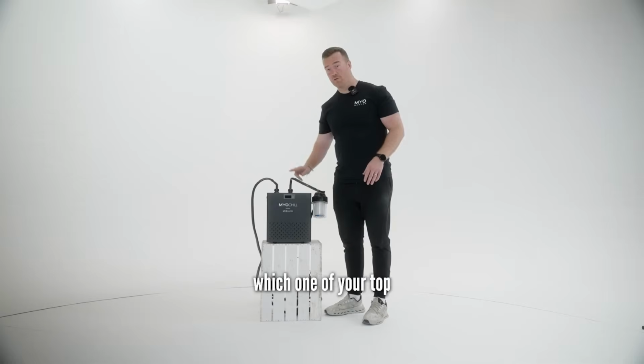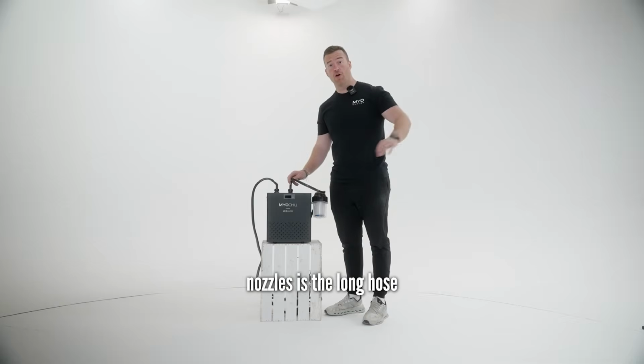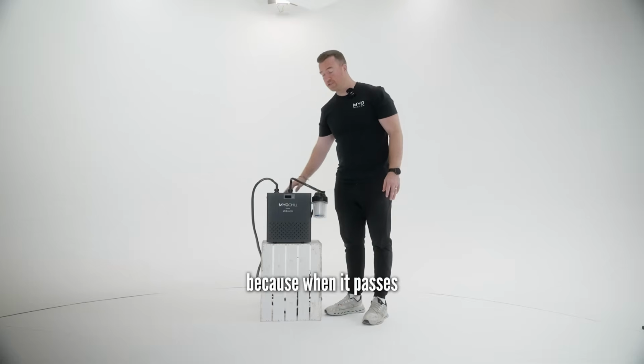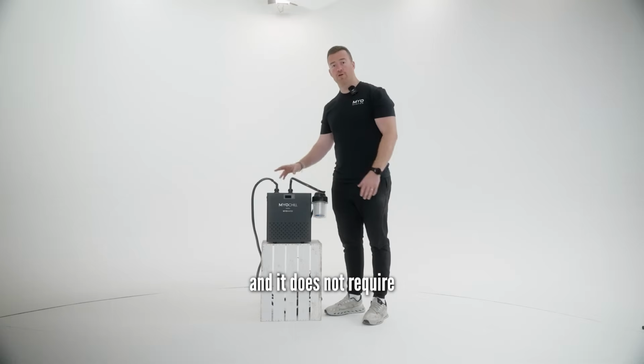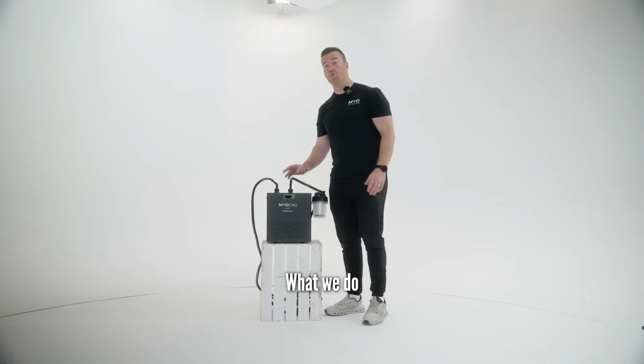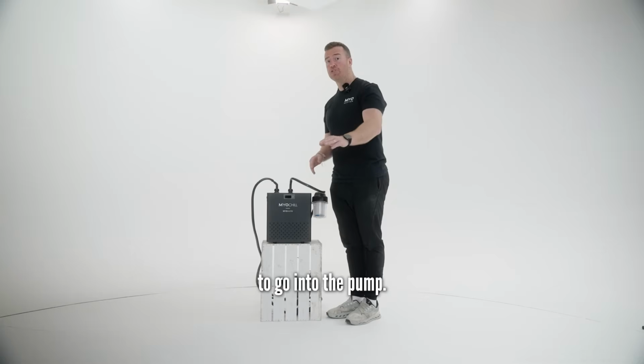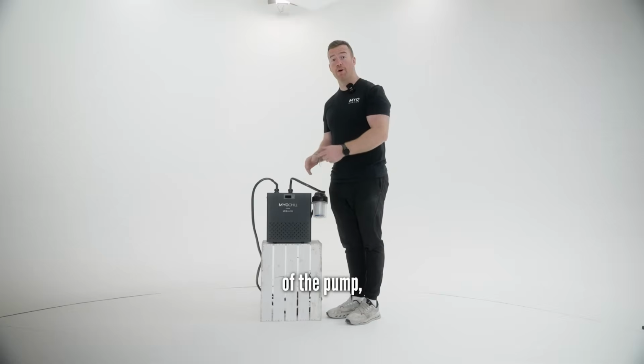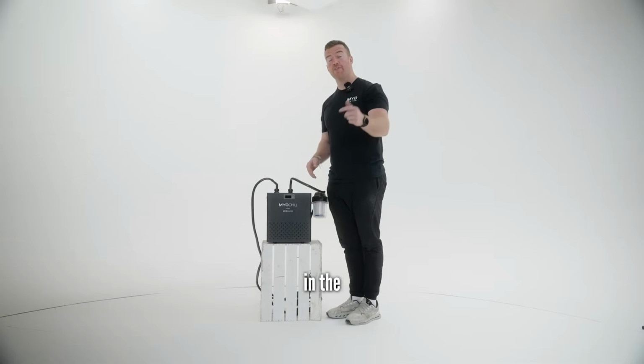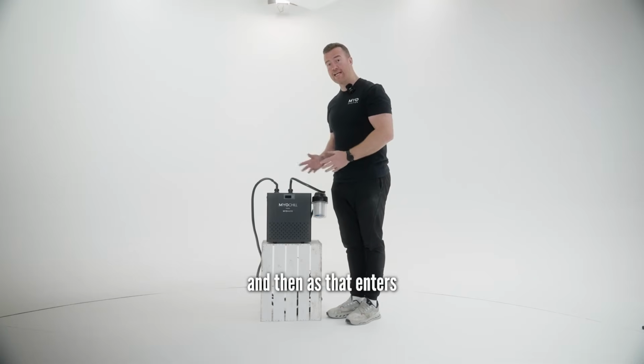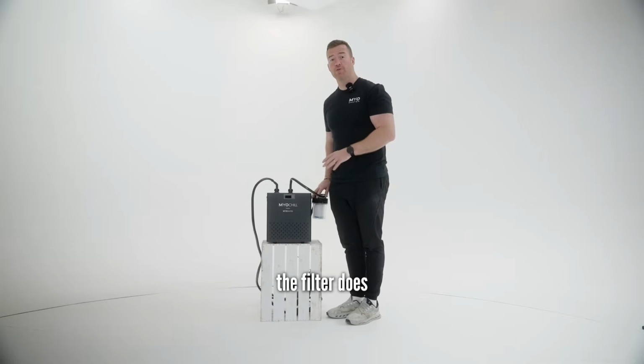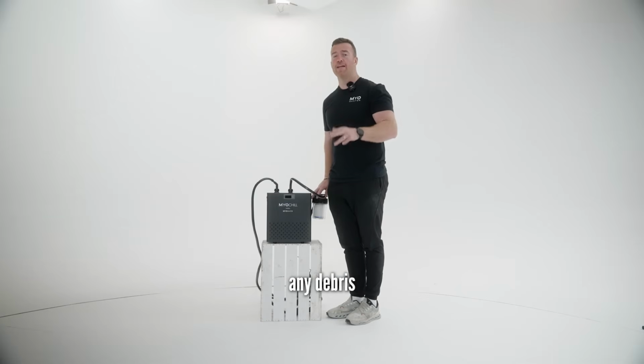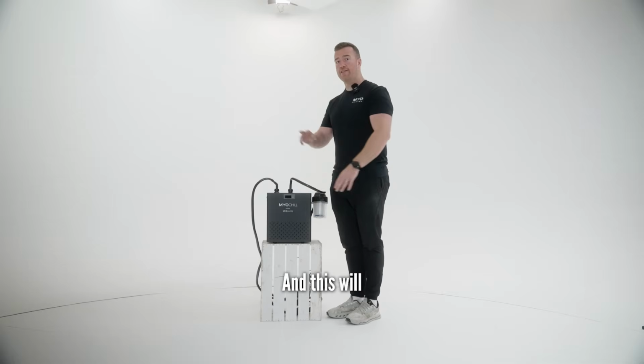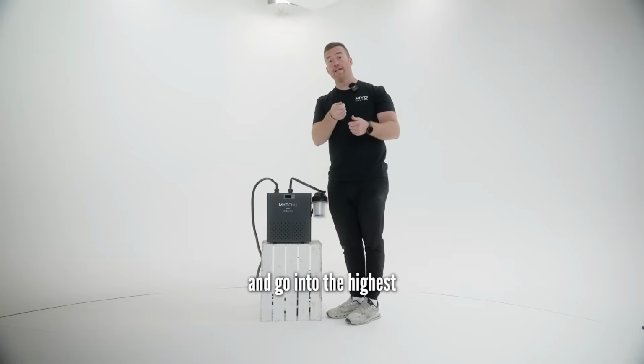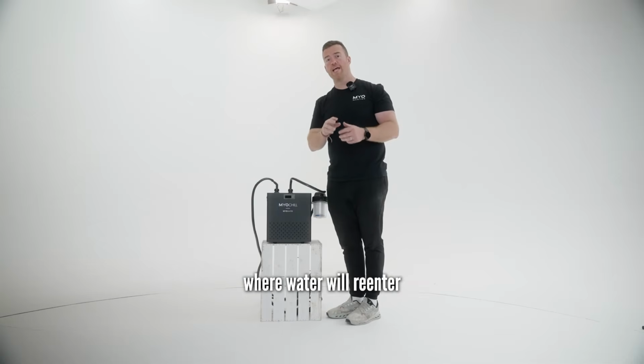So please remember key things with your chiller. It doesn't matter which one of your top nozzles is the long hose pipe or the short one, because when it passes through the chiller, it will chill and it does not require a certain direction. What we do need though is your lowest outlet to go into the pump. The direction of the pump arrow is away from the ice bath in the direction of the water, and then as that enters into the filter, the arrow on the filter does not matter. It will filter any debris no matter what. So the key one is your pump, and then it will go back into your chiller, and this will circulate round and go into the highest inlet on your ice bath where water will re-enter into the bath.